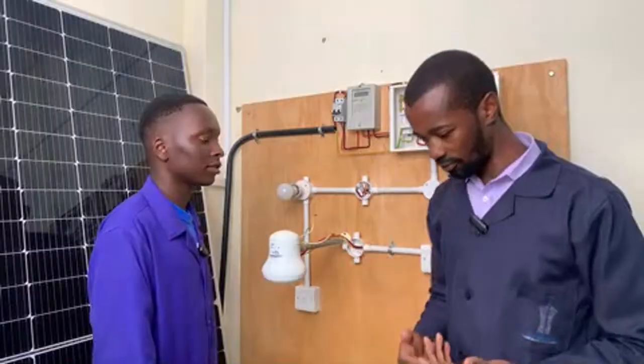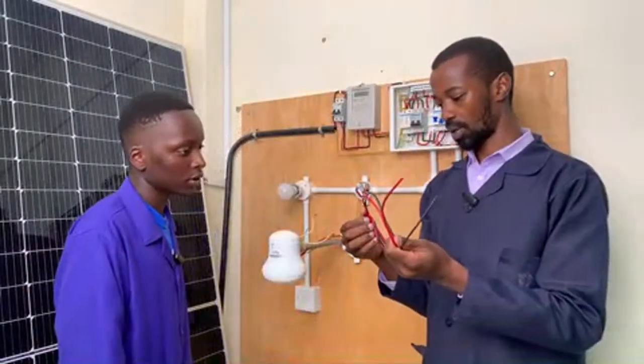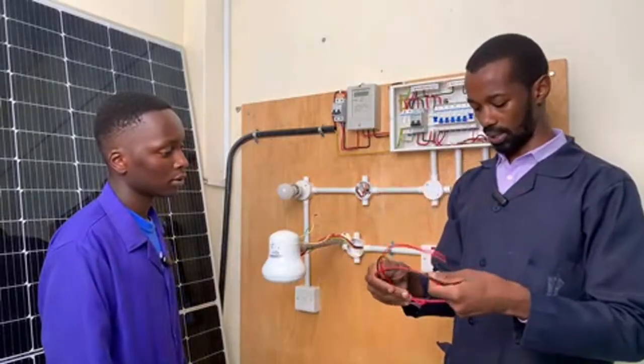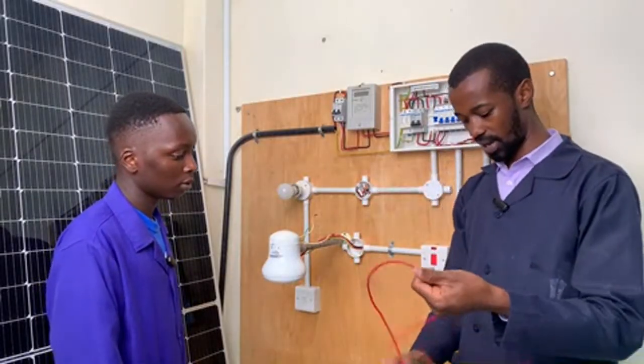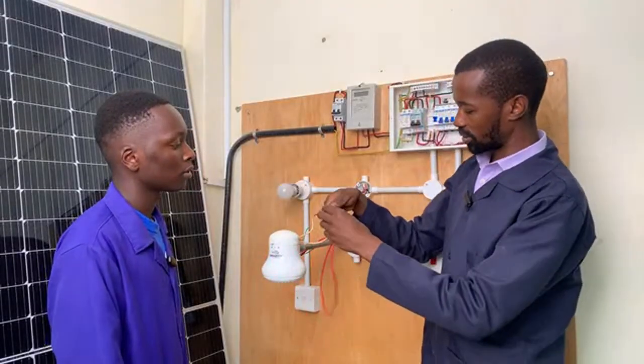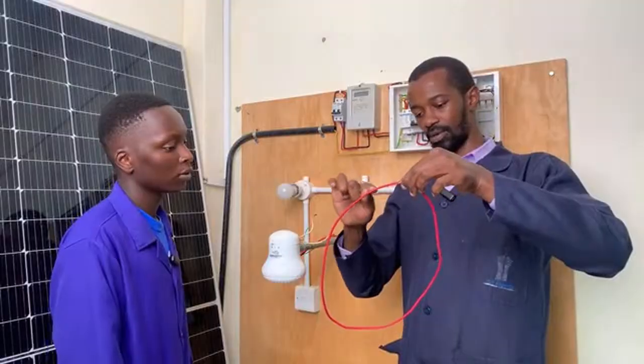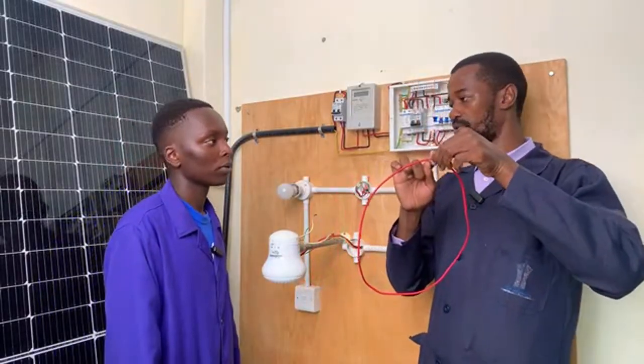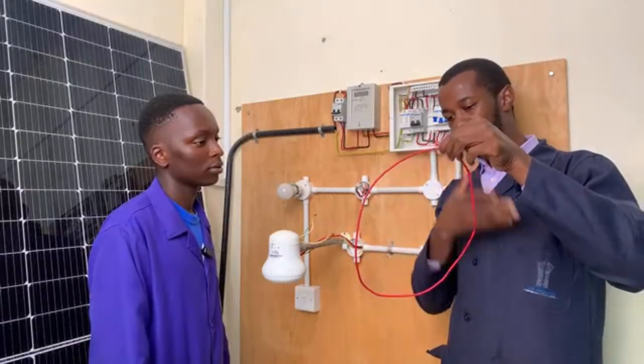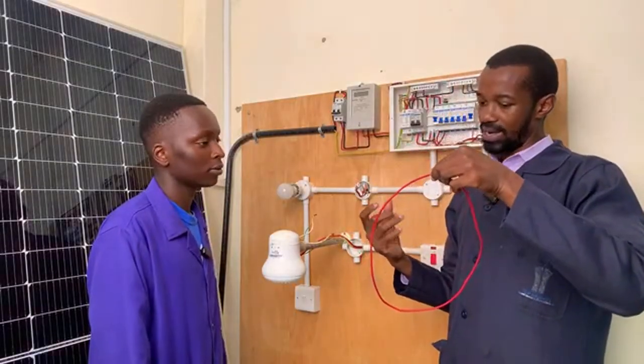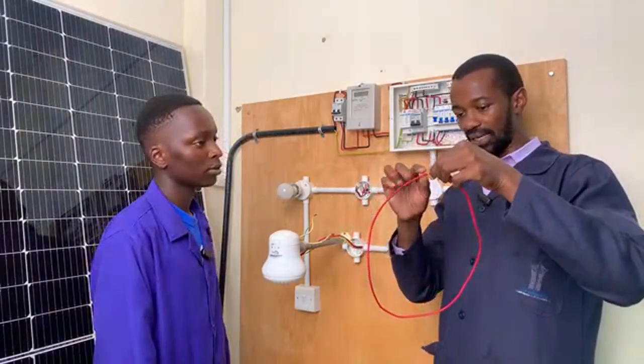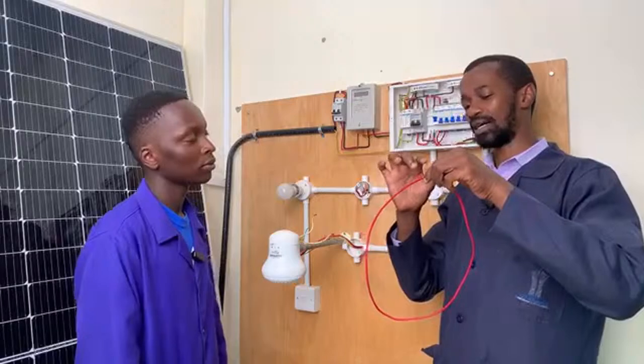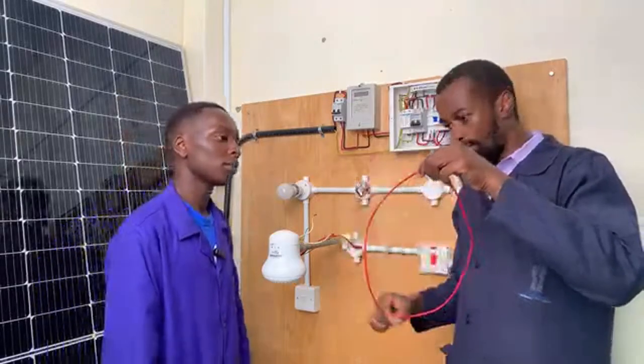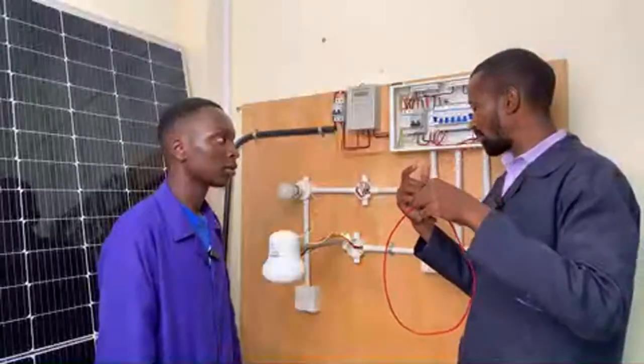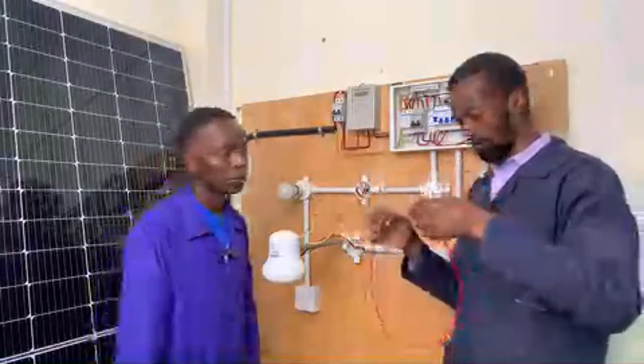Like you see, if we have this cable, electricity will flow in a loop connection. So let's say we have this cable here. Electricity will originate from point A, flow all the way, and then get back to point A. So whatever is in between here is meant to protect us. Now in this loop, if the electricity or current flowing is, let's say, 20 amperes, it has to go back to the source. Now the good thing about the RCCB, if you can show us, is that it has two main connections.